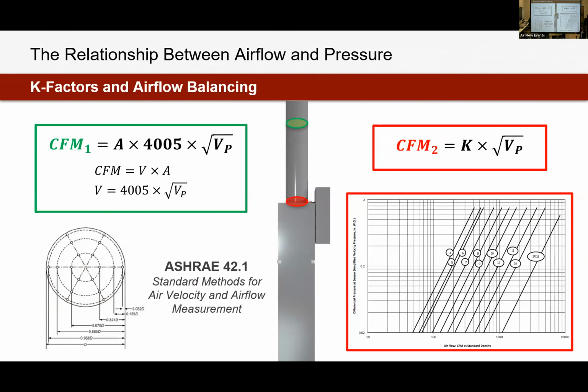How are we doing that? We're doing that with calibration curves. This calibration curve is something that a test and balancer would use on site. They are measuring the velocity pressure through that cross flow sensor and then correlating it to an airflow with constants. I know this graph is really difficult to see, but essentially all we're doing is relating the velocity pressure to an airflow with set constant lines. So this is how we're balancing the single duct in the field. And then usually they're doing a downstream measurement, maybe with a pitot traverse, as a second verification on the velocity there. So that's how we're using that airflow measuring device to find our airflow.